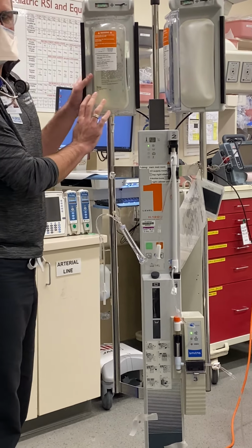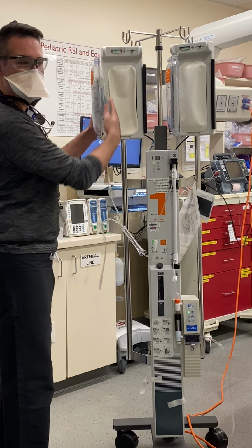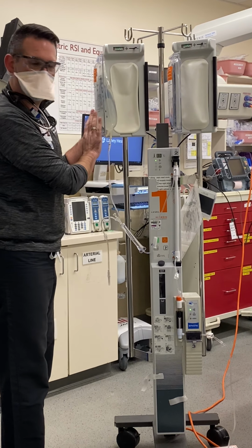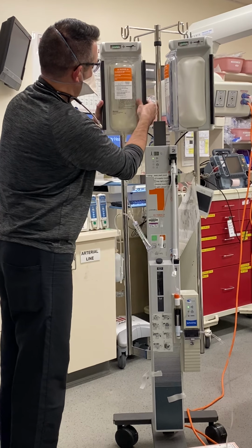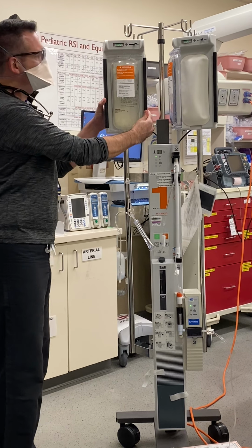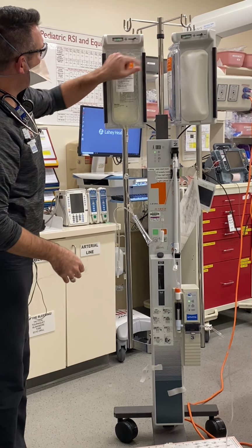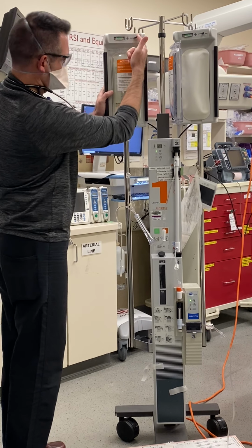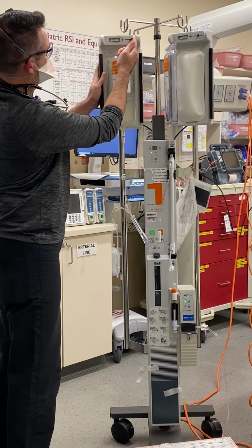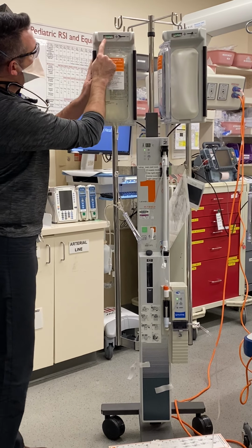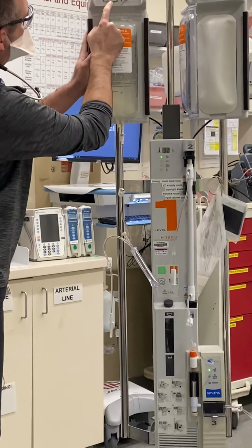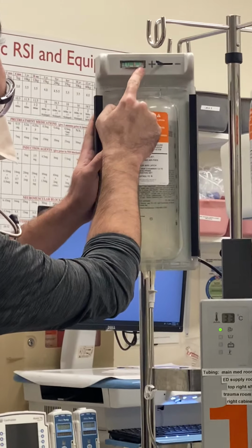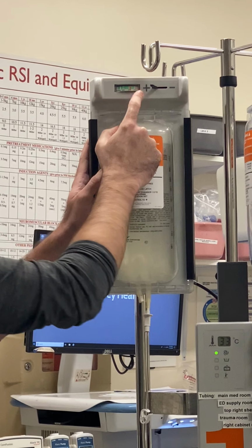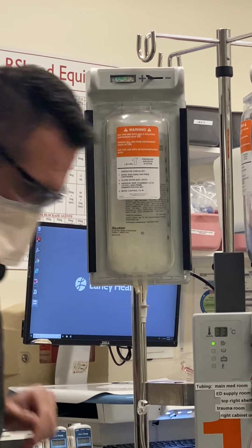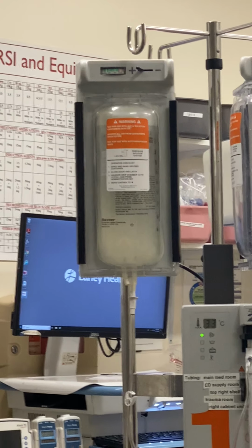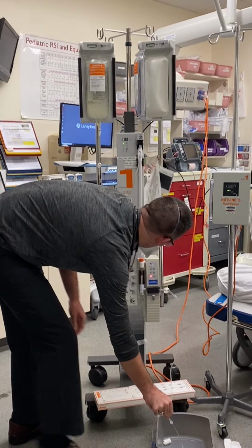If you're going to pressurize the fluids, again, hang the bag on this little plastic door, close the door, that's the latch, and then you can pressurize by using this switch up here. So, watch this. Watch the little pressure indicator go up. It ought to be between 200 and 300 millimeters of mercury. Don't go over 300 millimeters of mercury because you could end up really hurting the patient.